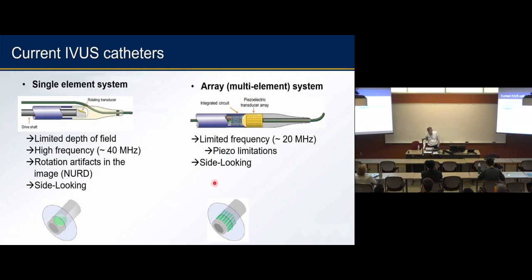If you look at the current IVUS catheters on the market, there are two types. One is a single element system. In this case, you have a single piezoelectric device, and it rotates really fast, actually 1800 RPM. If you take it out of the patient, you can hear this kind of sound. It's rotating, but it's in a sheath so that it doesn't touch the body. For this to work, you have to put saline between the transducer and the tube so that sound can transmit through. It usually gives better images, but people mostly use the array technology.